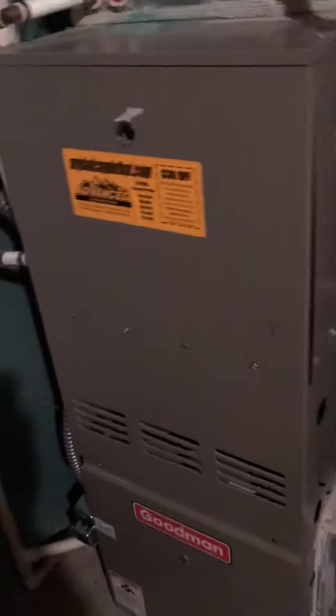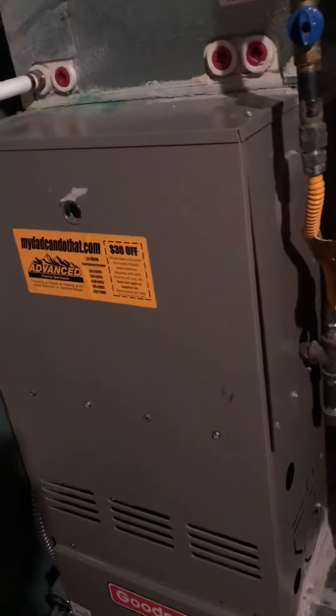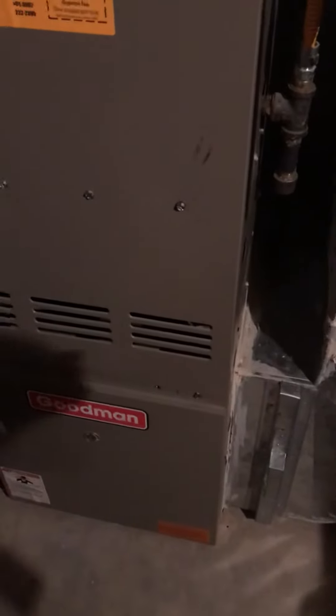I don't think the furnace is going to be an 80,000 BTU based on the age of the home and what we think the square footage is, but if it is we need to put it up on a base can, get some more airflow underneath it, replace the gas shutoff, replace the flex, and redo all this with a drip leg.